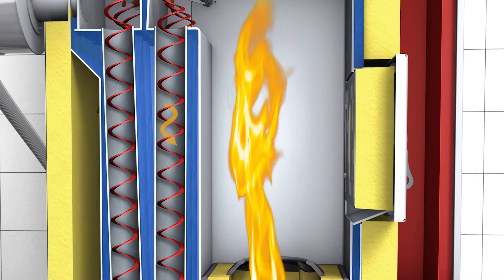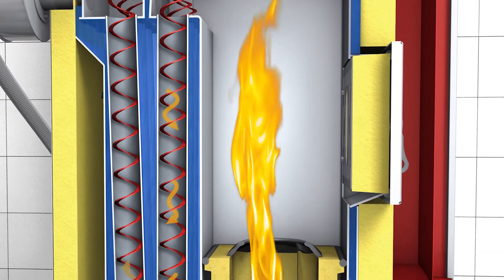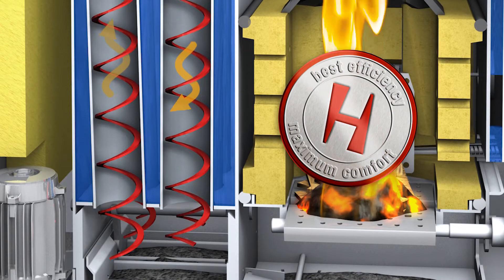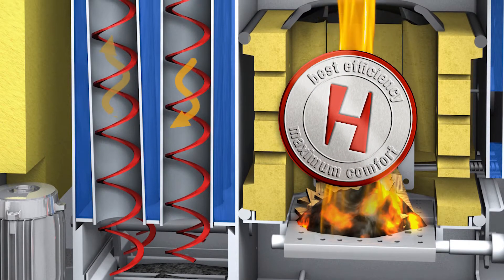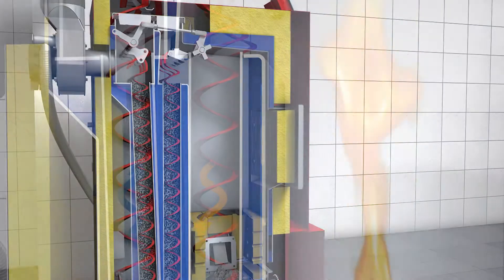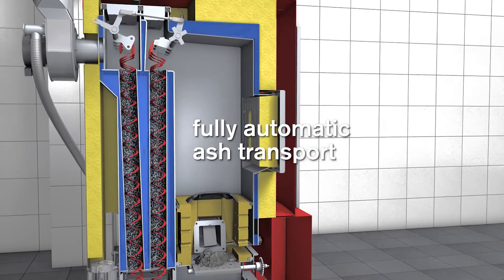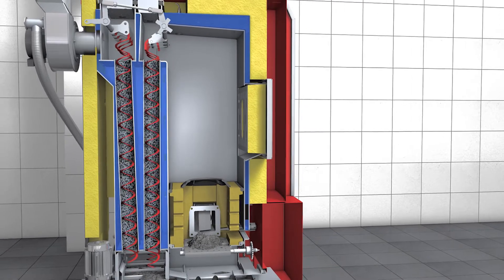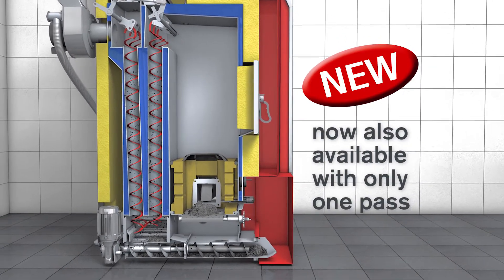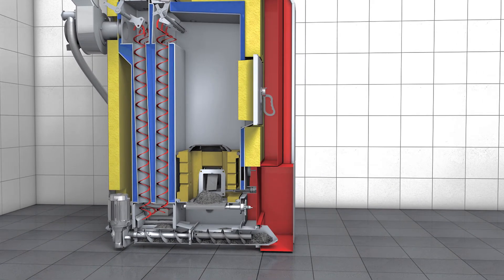Using 3-pass boiler technology, Hargassner guides the exhaust gas through fire tubes and vertical turbulators. Spiral turbulators enable maximum energy yield and minimal heating cost. The heat exchanger tubes are evenly cleaned by a defined up and down movement of the turbulators — all tubes are cleaned automatically. This causes continuously good heat transfer and guarantees constant high efficiency.